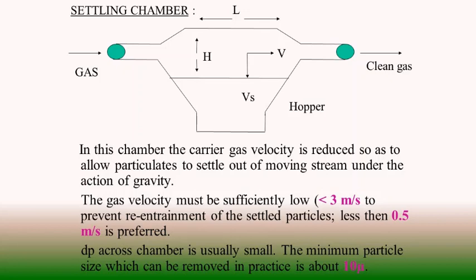Settling chambers are provided to settle down the dust particles in a flowing gas by sudden change in volumetric flow. With respect to dust-laden gas, a change in volume creates a change in velocity, and that causes the separation of dust from the flowing gas. The gas velocity must be sufficiently low while flowing through the settling chamber — below 3 meters per second is necessary for prevention of re-entrainment of the settled particle, and less than 0.5 meters per second is preferred.